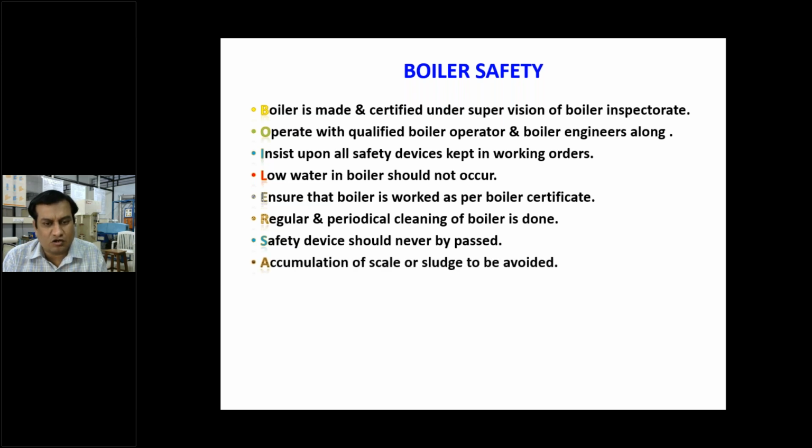Accumulation of scale or sludge is to be avoided. So in the water, you should check all the parameters before feeding the water in the boiler or in the drum. Due to impurities or due to materials like chlorides, sulfates, nitrates, etc., scale formation may be a problem, and due to some other weather conditions, sludge formation may also be an issue.